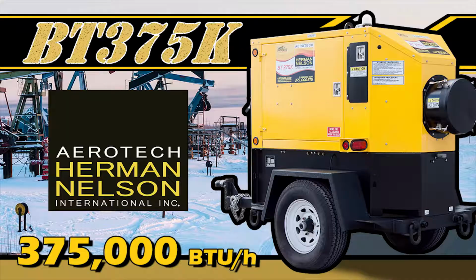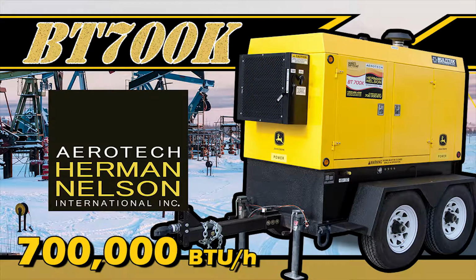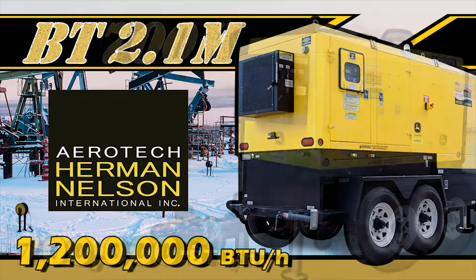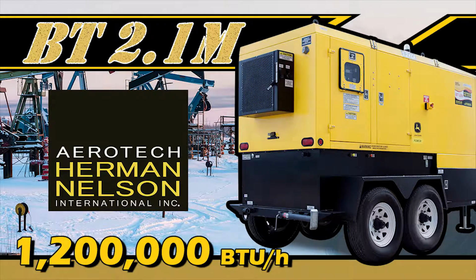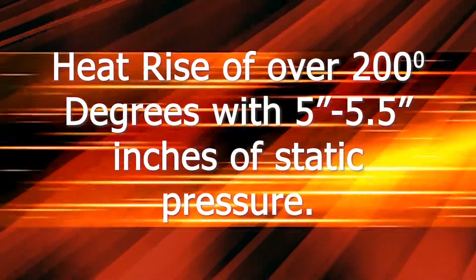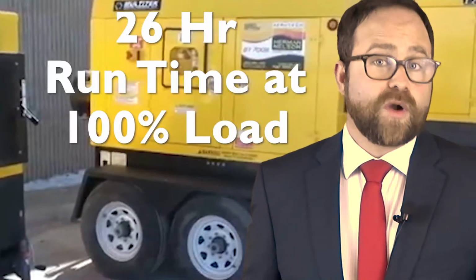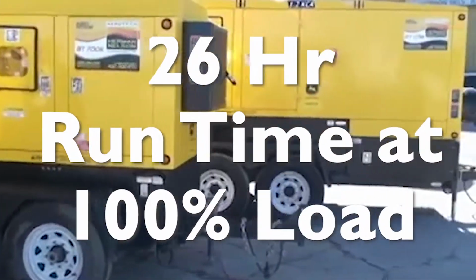Our line has several units that provide 375,000 BTUs all the way to 1.2 million BTUs. These high-quality flameless heaters will give you a heat rise of over 200 degrees with 5 to 5.5 inches of static pressure. In the field, these rugged diesel-powered units can be counted on to run 26 hours at 100% load.